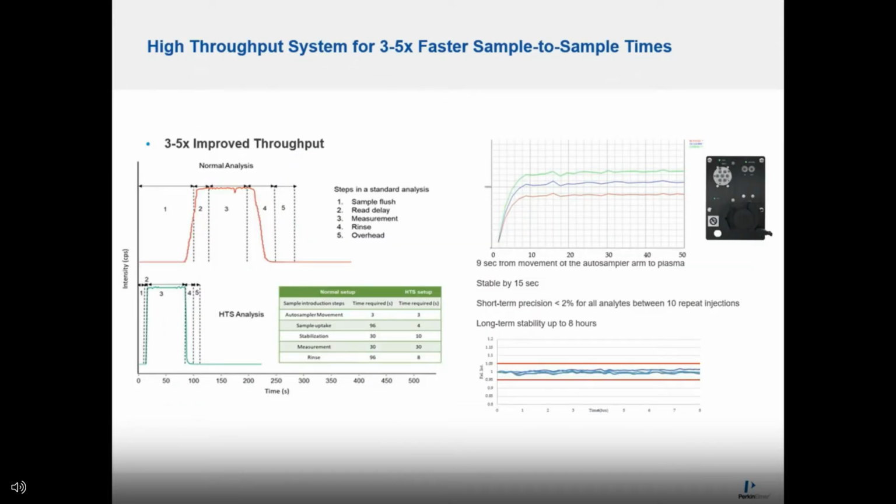Dilution is not the only way we can reduce the deposition on the cones. If we can keep the sample loading as short as possible, as it is required only during analysis, we will be able to prolong the intervals needed to clean the cones. One way of achieving this is by means of a flow injection technique.